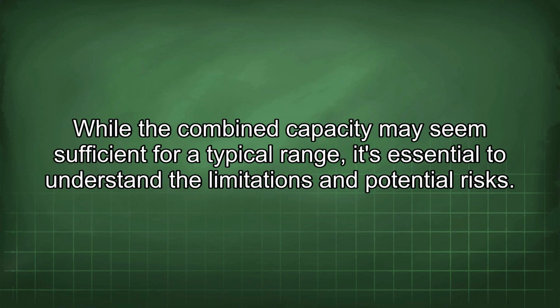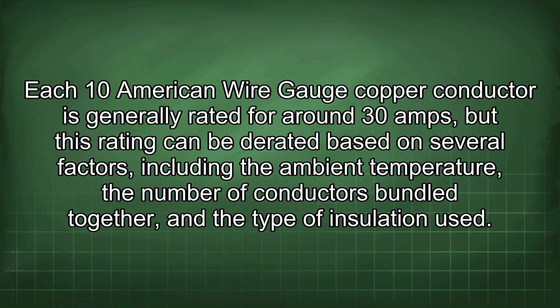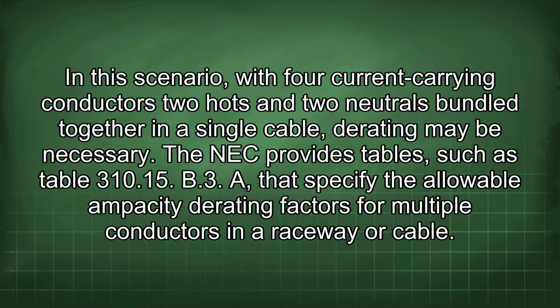While the combined capacity may seem sufficient for a typical range, it's essential to understand the limitations and potential risks. Each 10 American wire gauge copper conductor is generally rated for around 30 amps, but this rating can be derated based on several factors, including the ambient temperature, the number of conductors bundled together, and the type of insulation used. In this scenario, with 4 current-carrying conductors, 2 hots and 2 neutrals bundled together in a single cable, derating may be necessary. The NEC provides tables such as Table 310.15(B)(3)(a) that specify the allowable ampacity derating factors for multiple conductors in a raceway or cable.